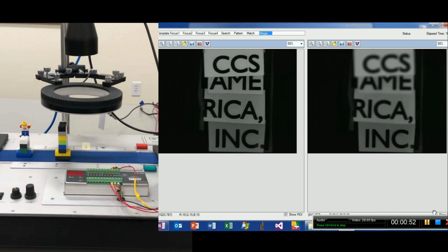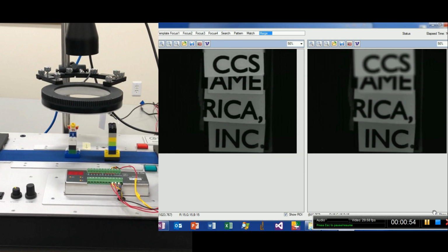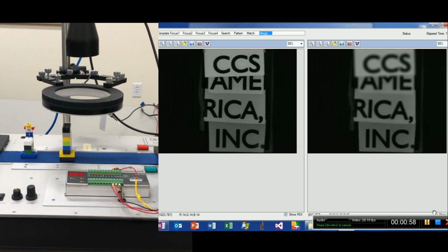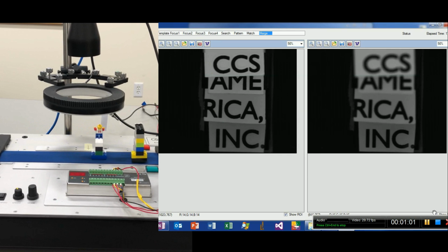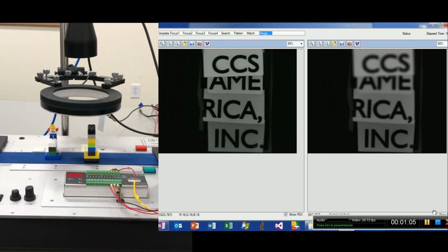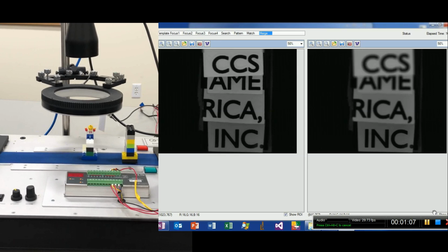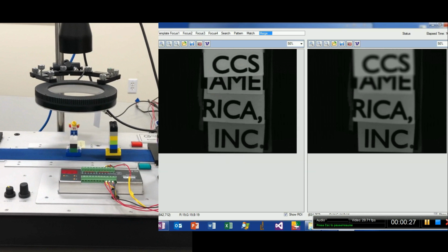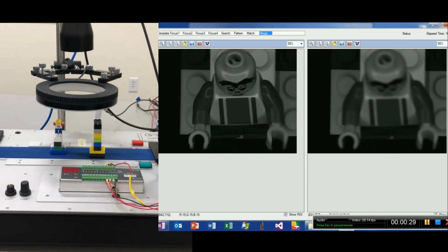The final depth of field depends on the focal range of the chosen lens and the number of focus images taken. This demonstration had a lens with a focal range of 20 millimeters, and we captured 4 images, so the total extended depth of field is 80 millimeters. Because of the depth of field overlap, the output image is in continuous focus over the entire sample.